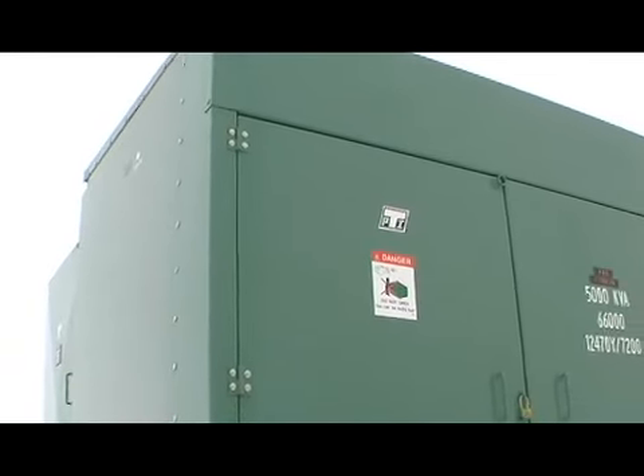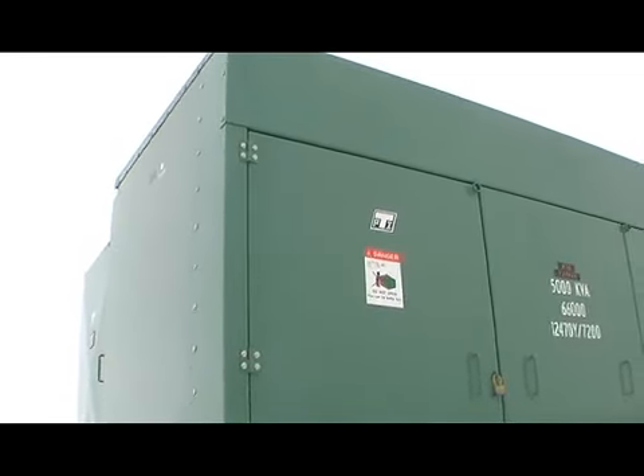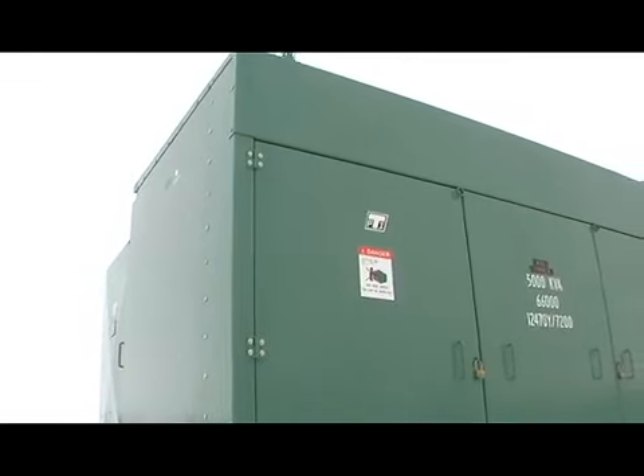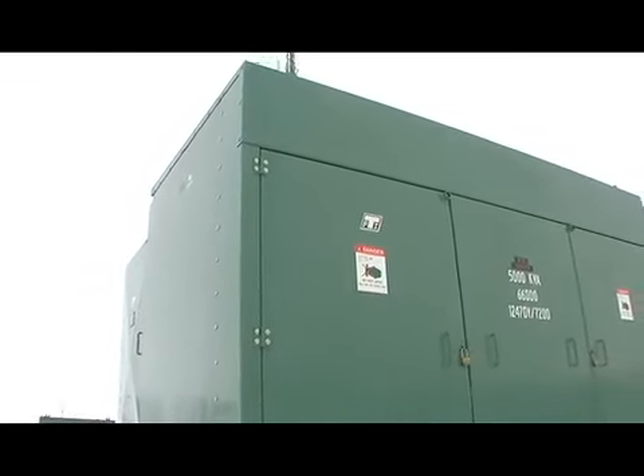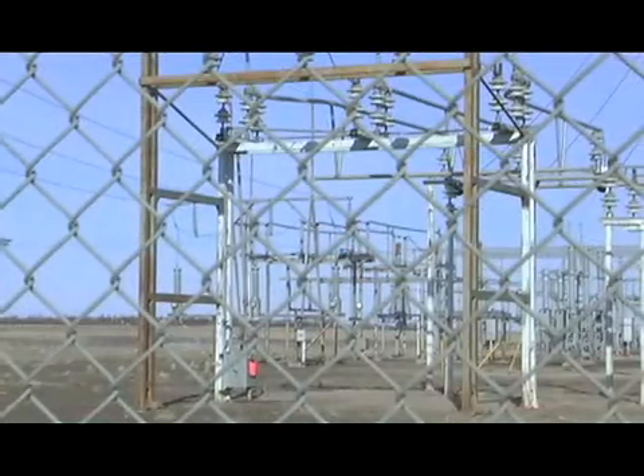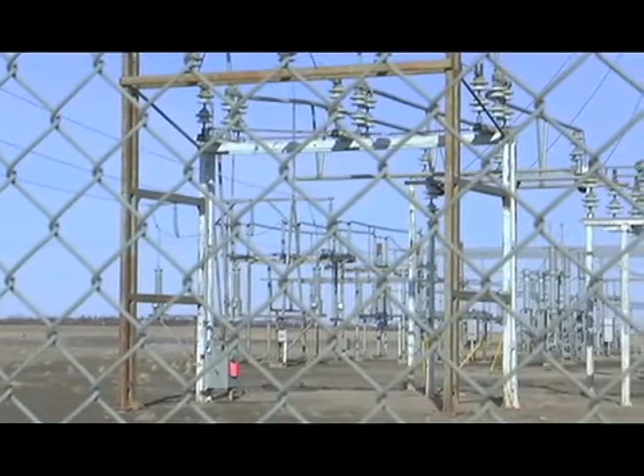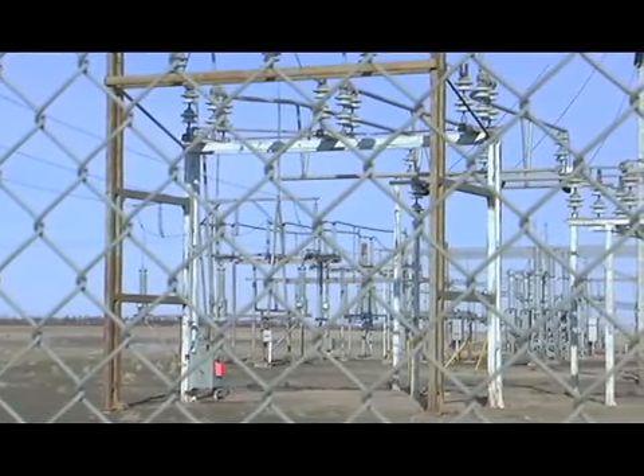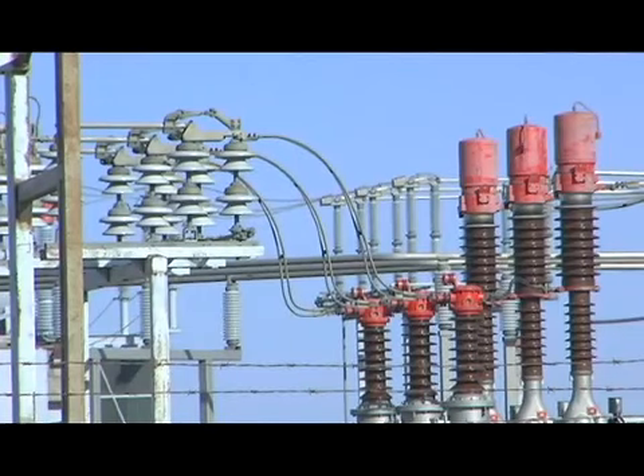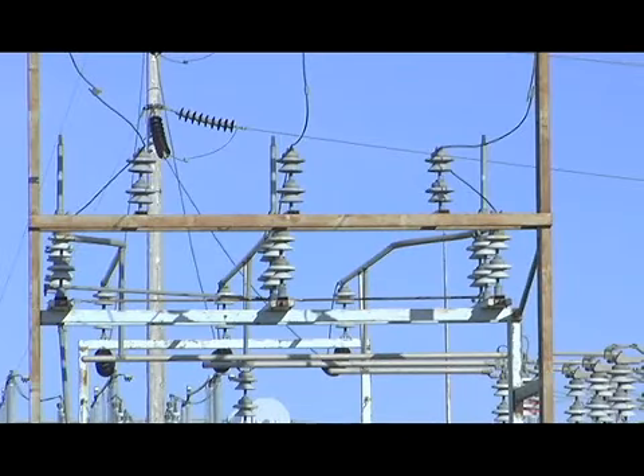The high voltage terminations are dead front and are completely enclosed by a tamper-proof structure. This makes the installation safe, requires less real estate, and eliminates the need for a fence, all of which combine to save time and money. Where on a conventional substation you've got all the exposed bus and live terminals that are subject to either wildlife or outage due to weather, this is all pad-mounted, tamper-proof, contained.